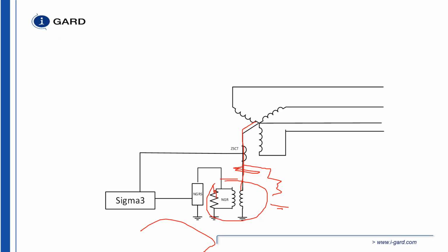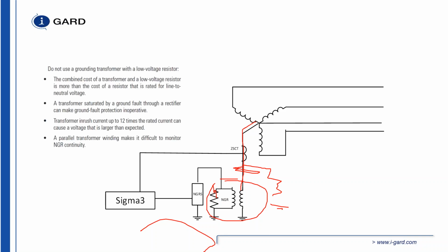transformer close coupled, because typically what you're going to do with this is you're going to have it for a high resistance grounding system. So the only time you want to have this close coupled is when you want to have pulsing. What my competitors say about this is that the combined cost of transformer and low voltage resistor is more than the cost of the resistor that is rated for a line to neutral load. In short, that's their way of saying they can't monitor the resistor and the neutral at the same time.